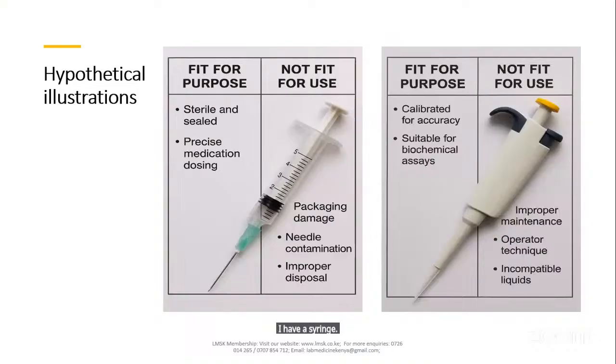This syringe has been produced by manufacturers. The manufacturers of this syringe, before deploying it to the market for circulation, indicated that in their controlled laboratory setting, the syringe performs as per requirements. So it has met the concept of fit for purpose. But then it is our responsibility as the end users of this product to ensure that the product is fit for use in our settings.